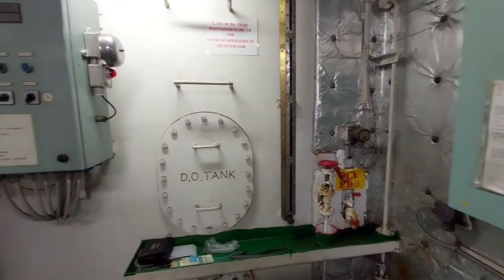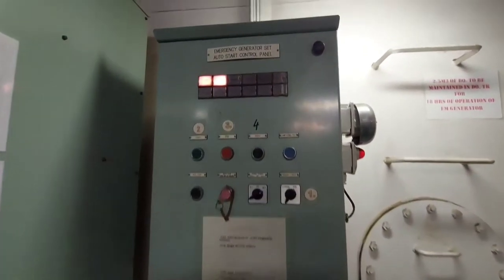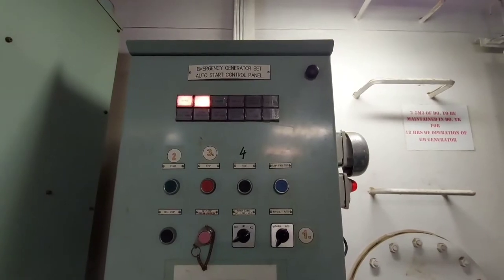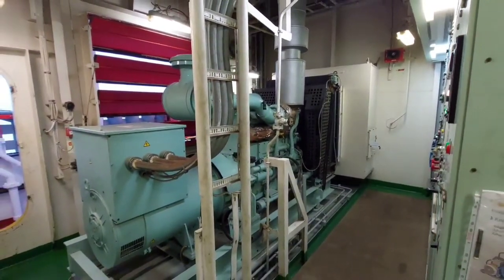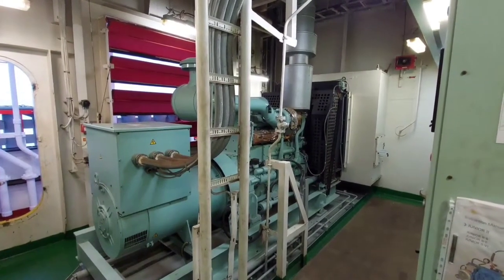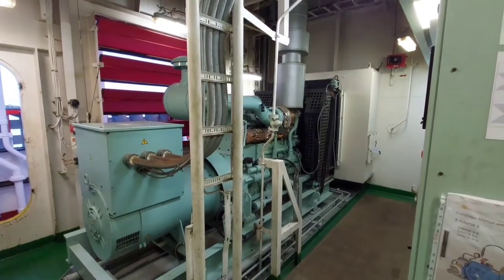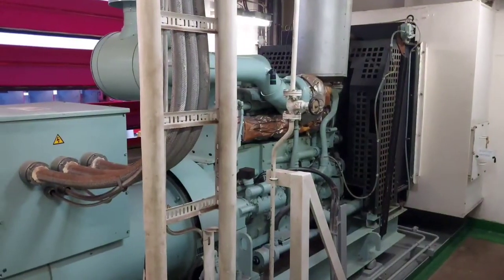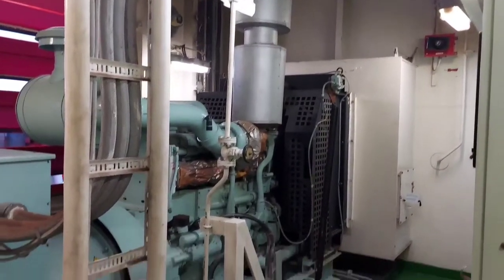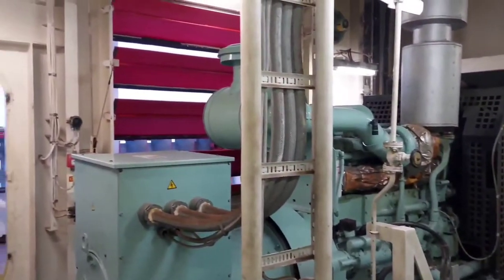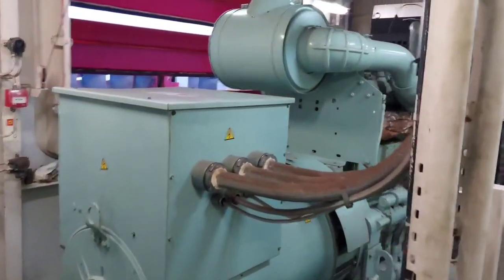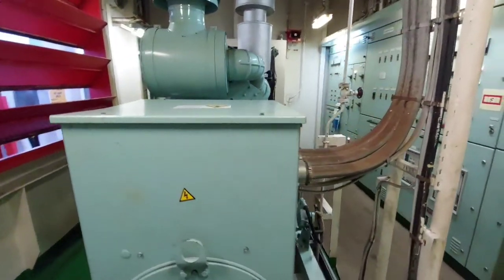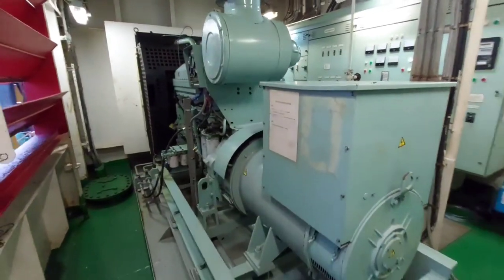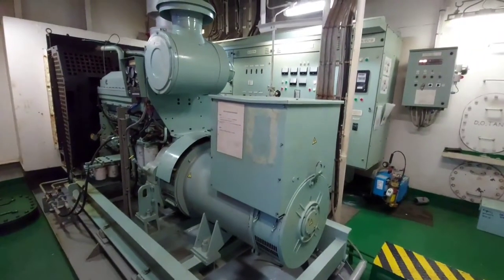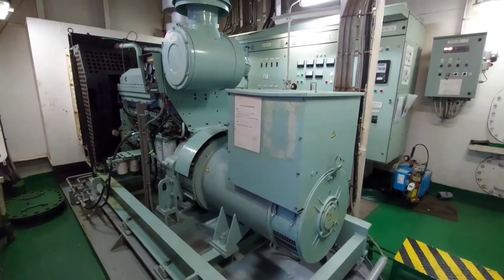You can see the starting panel of the emergency generator. This generator will be normally kept in auto mode. When a blackout occurs, that means if our running generator or our main generators are not operational, at that time this generator will come on load automatically and it will give the emergency supply to the ship. Lots of regulations are there for this emergency generator, and this is one of the important safety equipment on board.